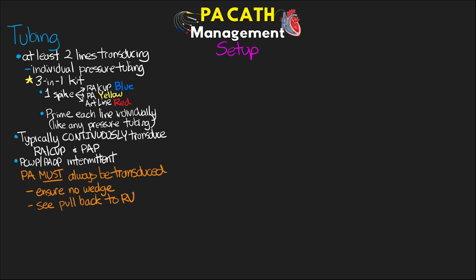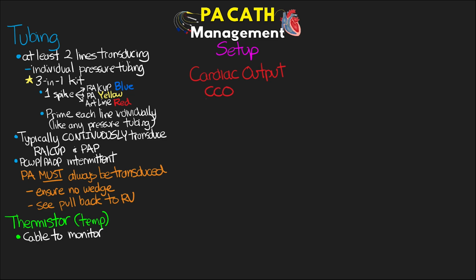Now, depending on the capability of your catheter, you're probably going to need some other pieces of equipment. So if it has a thermistor to record temperature, then there's going to be a cable to send that back to the monitor. If you have a thermistor, then more than likely you're also going to be doing cardiac output measurements. So if you are fortunate enough to be utilizing a continuous cardiac output swan, then you're just going to need another cable, and it's usually combined with the thermistor one to connect from the monitor to the catheter. Now remember that it's this specific wire that actually sends power to the filament to actually heat up on that swan.